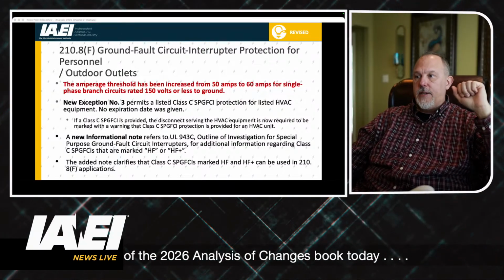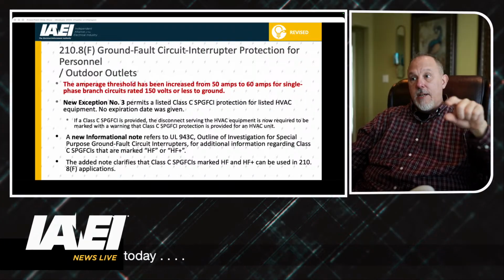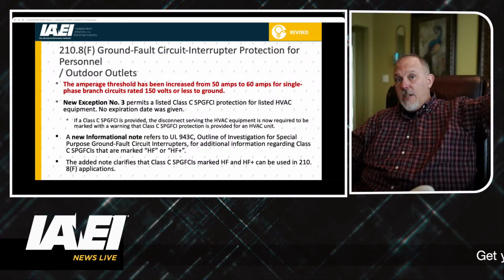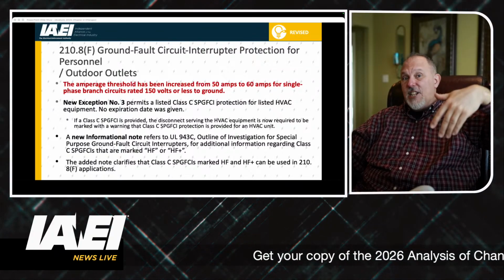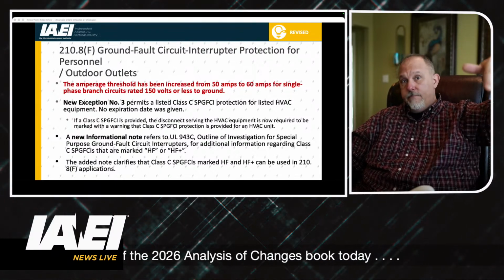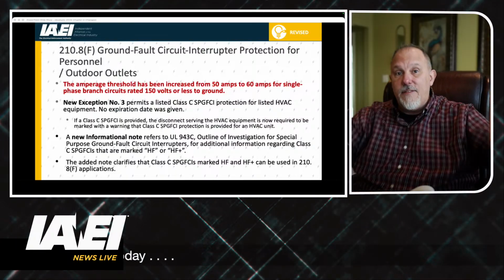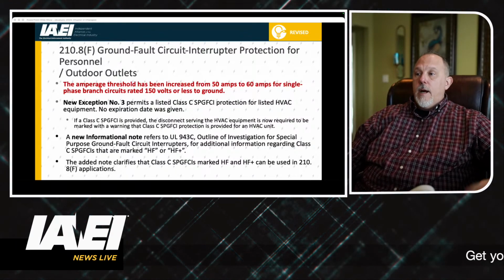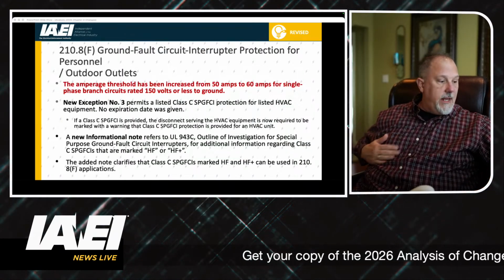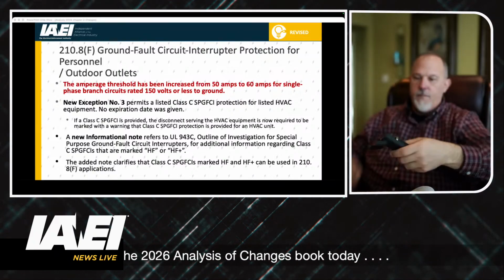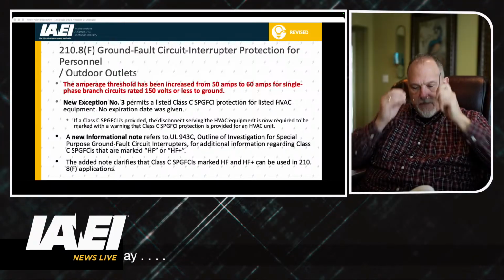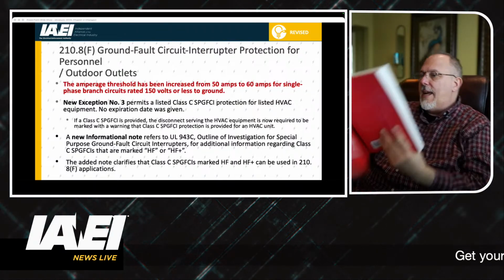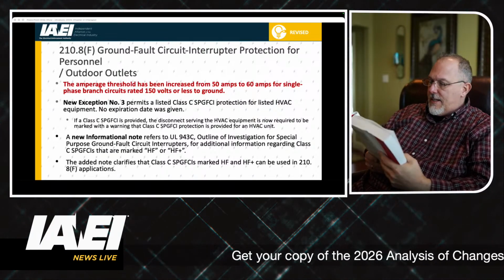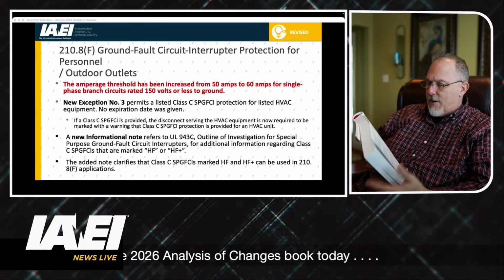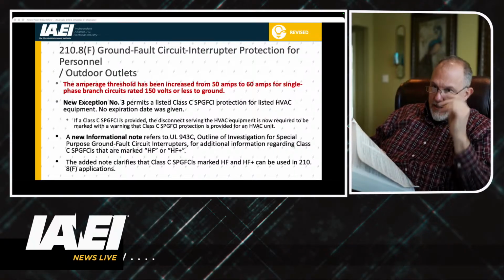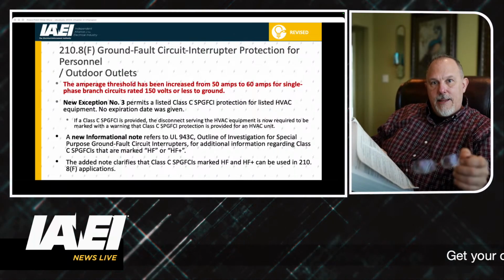There's no expiration date that's given. There is, again, an informational note that tells you, hey, if that Class C GFCI, which is listed to UL 943C, is marked HF, bada bing, bada boom, bada bang, it's still a Class C GFCI, so it can be used. Right? And it's an informational note for the same reasons that we said before. What else? 210.8F. We said the date is in there still for listed HVAC equipment that has the exception, and it will expire September 1st, 2026. So they did not renew or extend the expiration date.